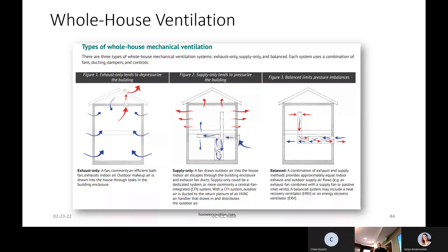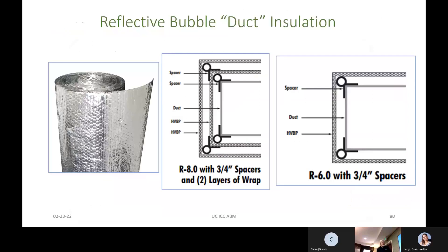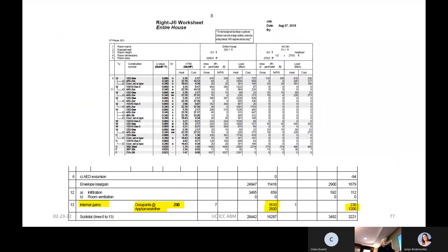Mechanical ventilation needs to be accounted for if they're providing it in the house — it needs to be on your load. If we had not amended the energy code in Utah, every house would be blower door tested and every house would have to reach a tightness level that requires mechanical ventilation. We have an amended code that gives options so we don't have to trigger mechanical ventilation. But every house built today really should have mechanical ventilation to minimize the chance of condensation in walls and to maintain air quality.